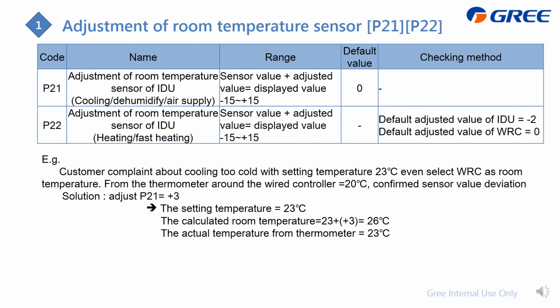Adjustment of room temperature sensor. This is the correction value. P21 is for cooling, dehumidify, and air supply. P22 is for heating. The range is plus or minus 15. And according to this, you can also meet the customer's setting.